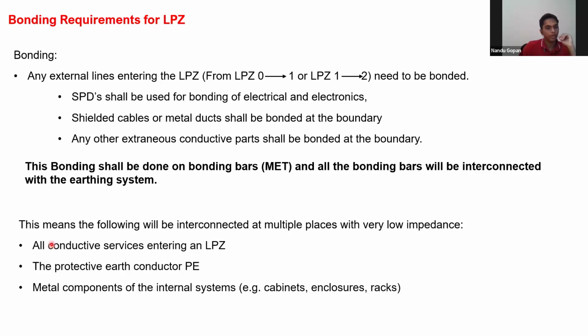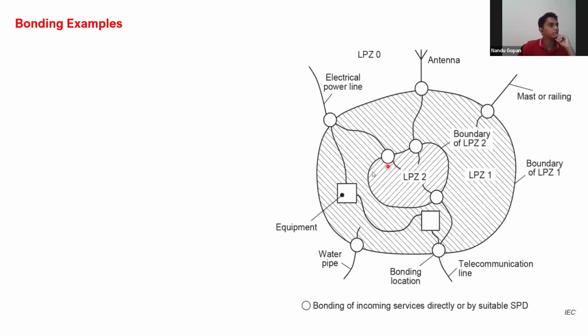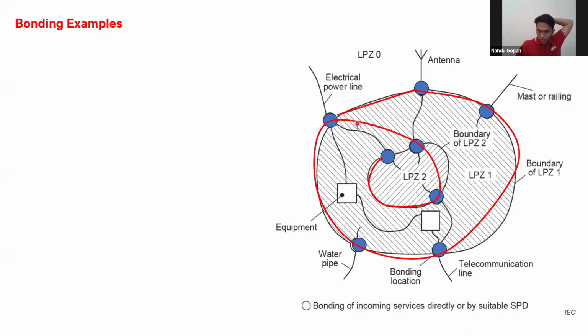So here I've noted that all conductive services entering the LPZ should be bonded. This is an example of bonding - here's the boundary, this is outside LPZ zone 0, this is zone 1, and this is zone 2. If there's any mast, railing, antenna system, electrical power lines, pipelines, or telecommunication lines, you are supposed to bond it using an SPD. In some cases you don't need an SPD - you can just bond it to the MET or similar. All these bondings are interconnected together; they should not be left separate, they should all be interconnected.